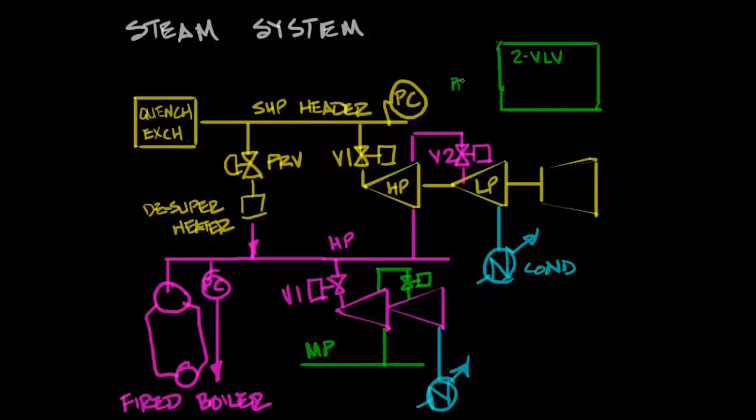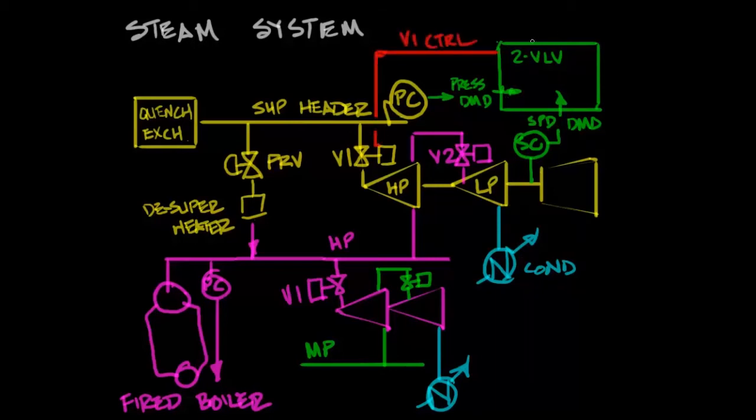Looking at our two valve algorithm it's going to take a pressure demand from a pressure controller on the SHP header and a speed demand from a speed controller that's watching the turbine speed. The output of that two valve will send an output to control V1 and another output to control V2.